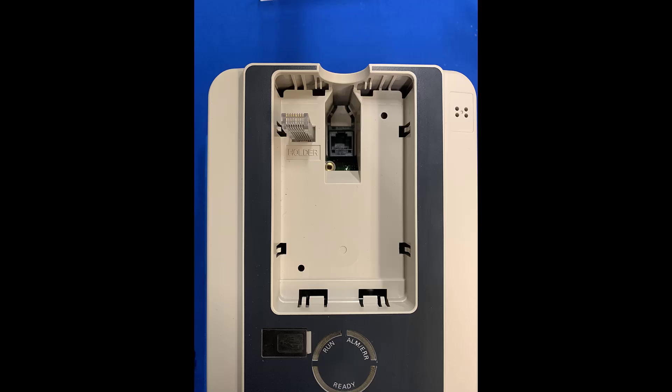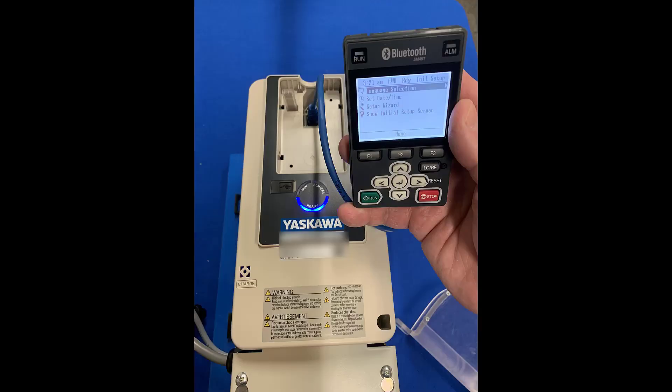Do not, I repeat, do not under any circumstances use the port that the keypad is plugged into as the Ethernet connection. It may look similar, but it will damage your PC. So again, if you're connecting Ethernet to your computer, use an Ethernet option card and follow the instructions to set that up.